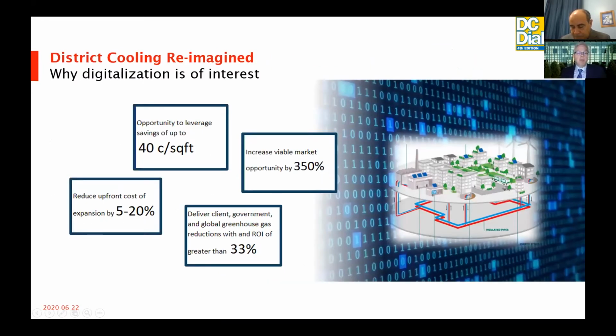So why might people be interested? What can digitalization do for us in our district cooling facilities? It can actually reduce the upfront cost during design and construction by 5 to 20%. And I'm going to explain how that works. It can improve the efficiency of the full network, up to 40 cents per square foot of living space. So of the service space, the building space, 40 cents per square foot per year. Quite a significant number. It can increase the market opportunity by 350%.